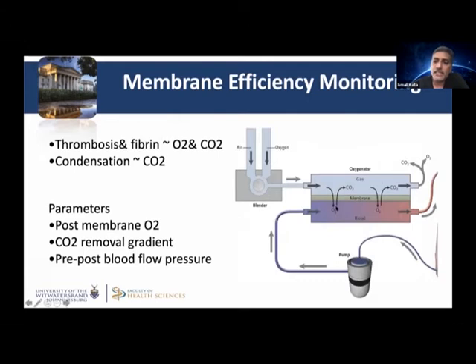So what affects the ability of this oxygenator, or this lung, to function properly? The most important thing is condensation within the oxygenator, within the chamber, and thrombin and fibrin formation along the membrane that actually affects the diffusion of gases. So what you must remember, as opposed to a CRRT circuit, to the best of my knowledge, the kidneys or the dialysis chamber that you use functions for a maximum of maybe 72 hours to 96 hours.